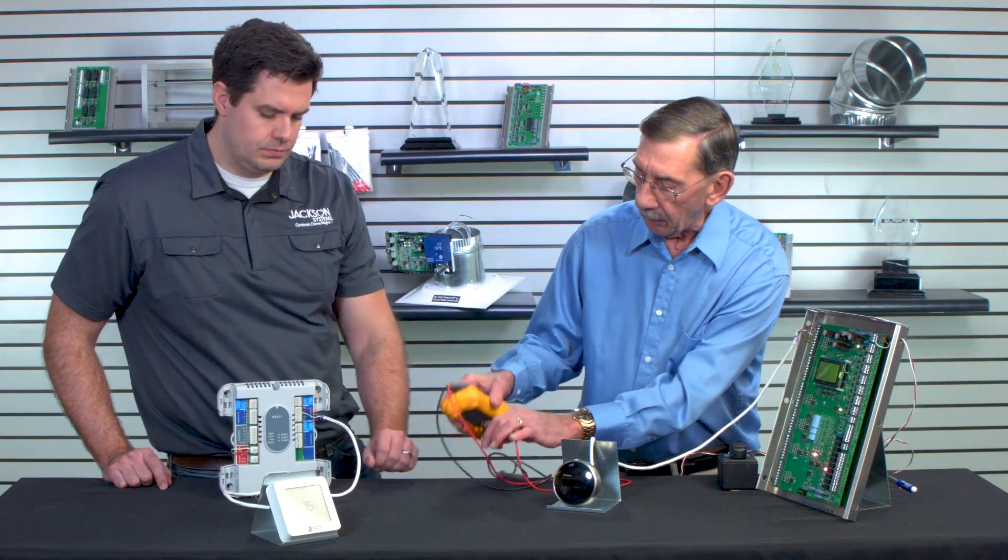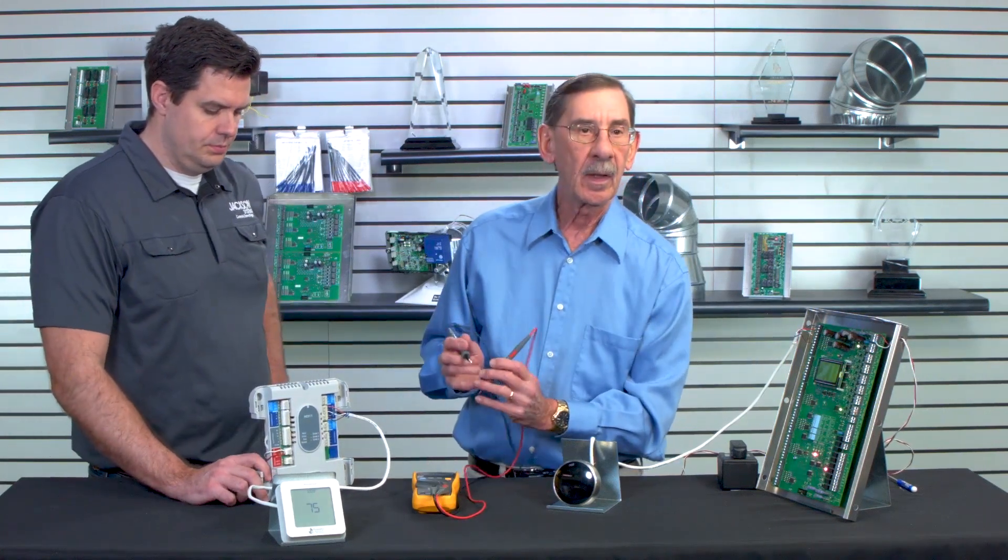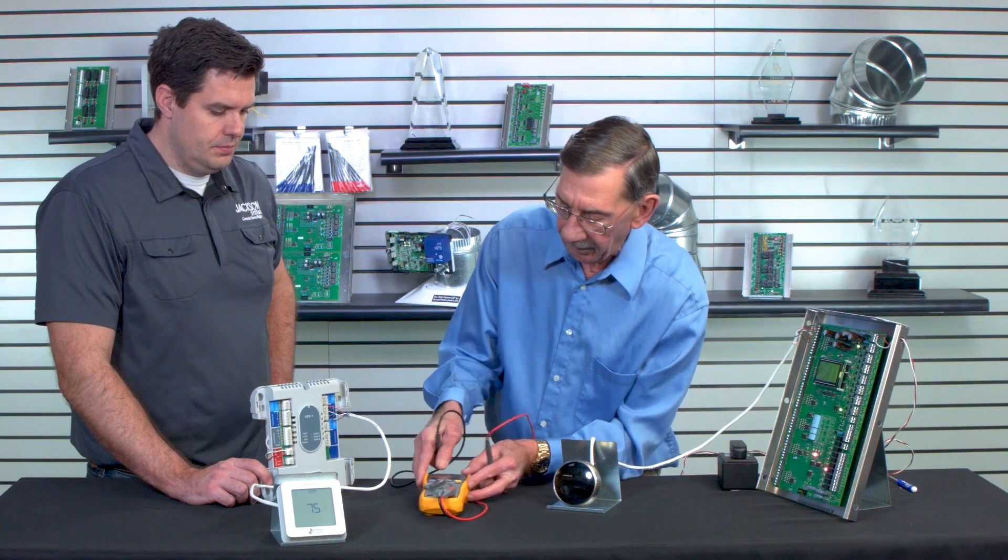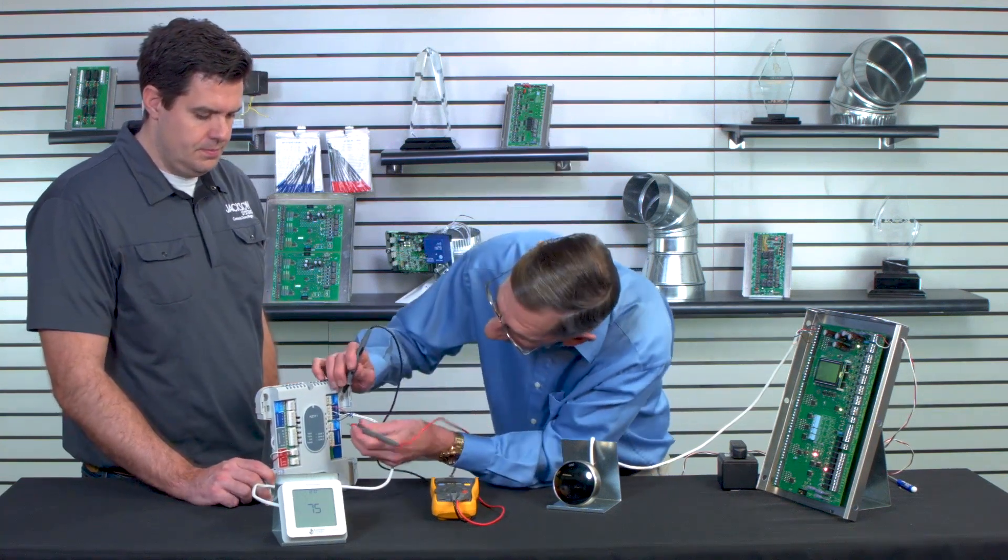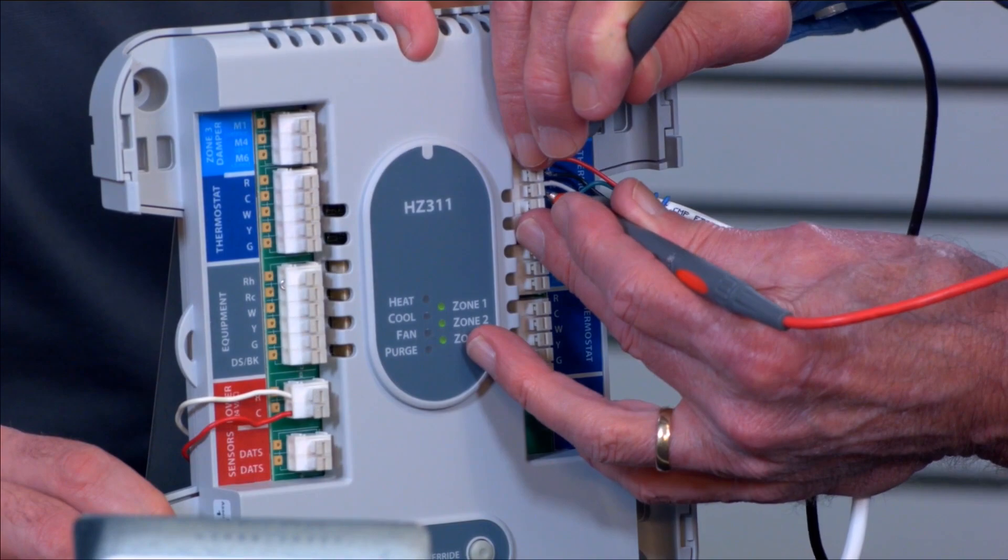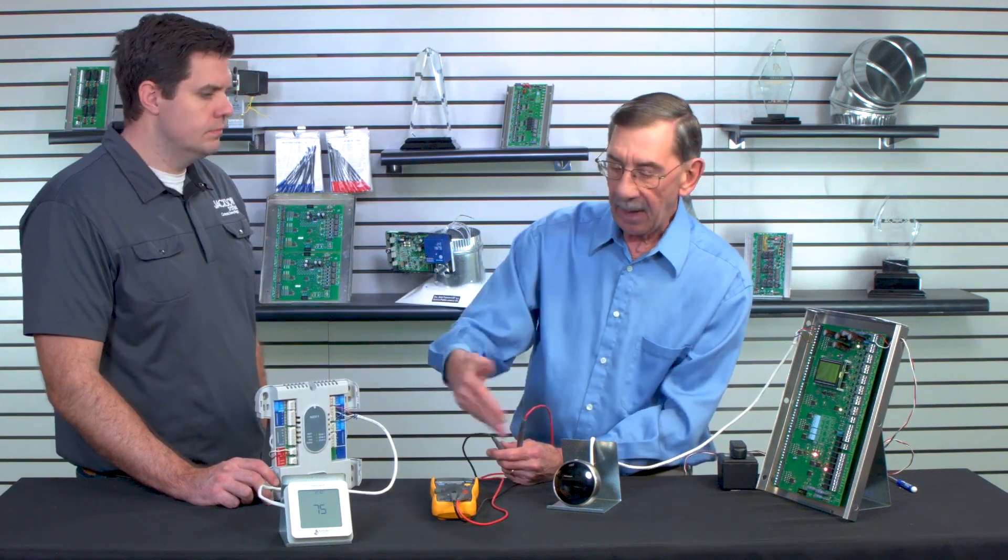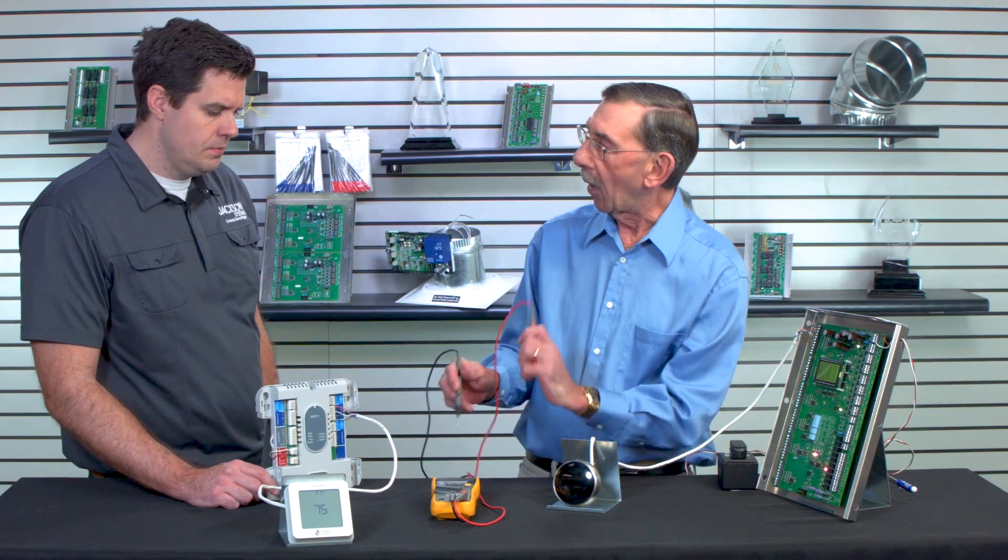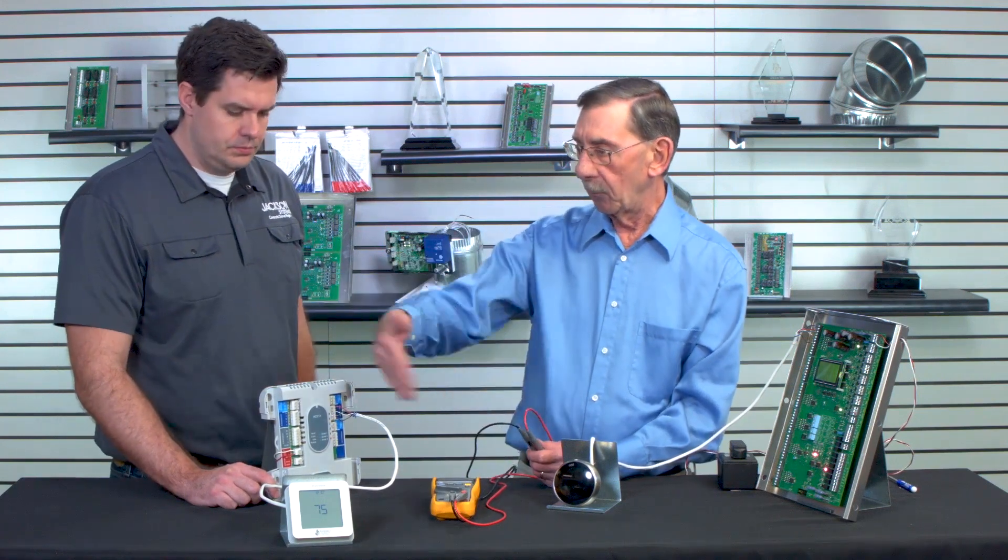Honeywell on their panels, we can do the same thing. They use these really cool quick connect terminal blocks. Well, it's hard to get a probe in there. So if I were going to test a Honeywell panel, same thing, they have these little pads and they're really cool because I can go across these pads and measure voltage and I can confirm that the thermostat is inputting the call to the panel. And the same thing goes with the outputs. I can check the HVAC equipment outputs, go ahead and go to tone and go across R and W. If I get tone, I know it's outputting. The relay's made. And then from there, we have to go to the equipment or the wire that runs to the equipment.